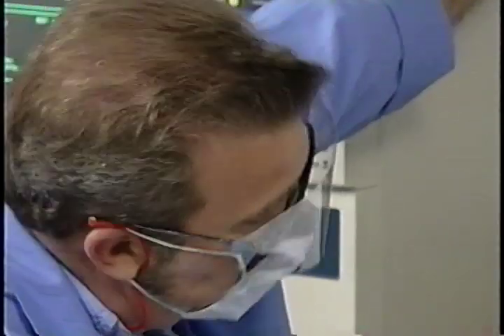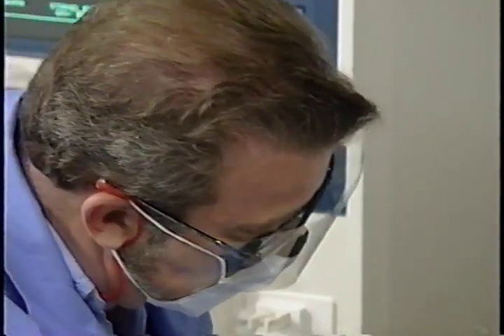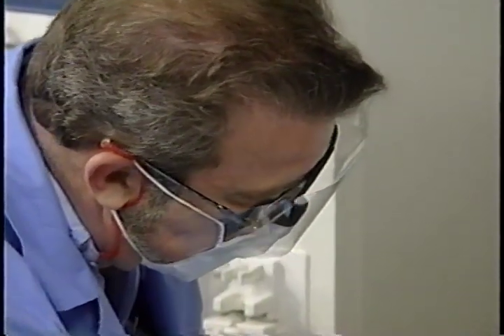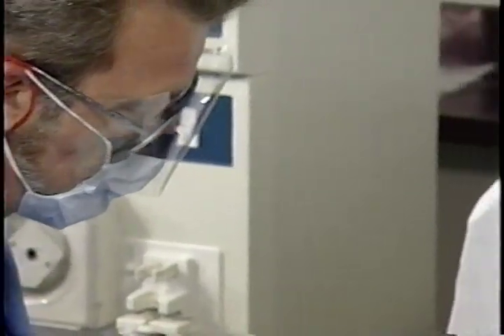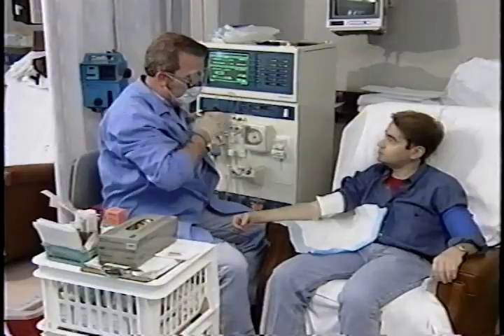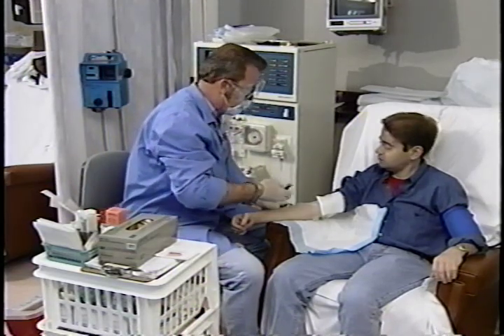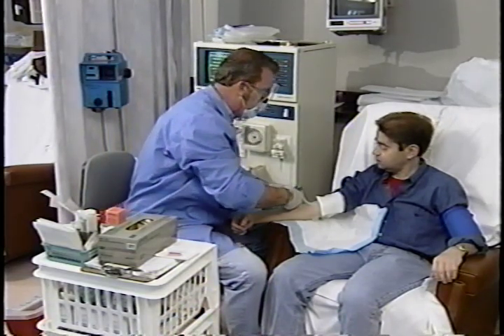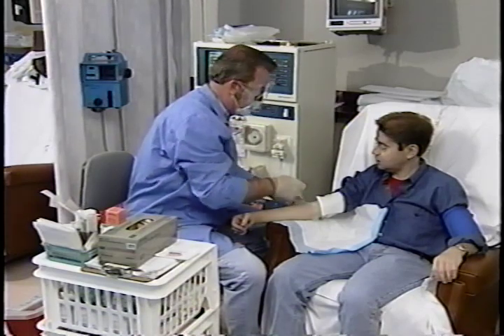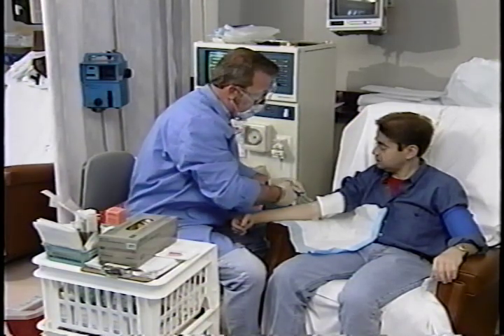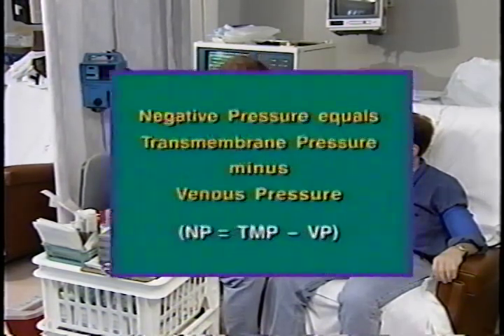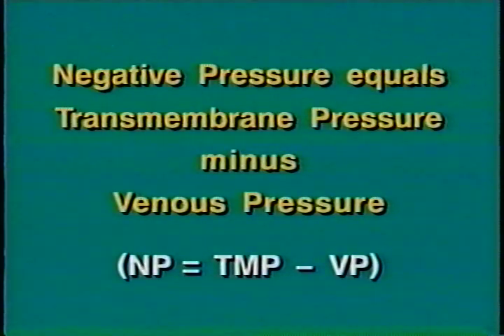Fluid is removed during dialysis by means of transmembrane pressure, or TMP for short. TMP is calculated using the ultrafiltration coefficient provided by the manufacturer of the dialyzer, the dialysis time, and the amount of fluid to be removed. TMP is set on the machine as either TMP or negative pressure. If your machine requires that negative pressure be entered, it is calculated as follows. Negative pressure equals transmembrane pressure minus venous pressure.